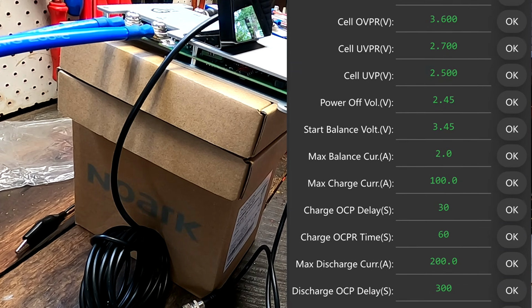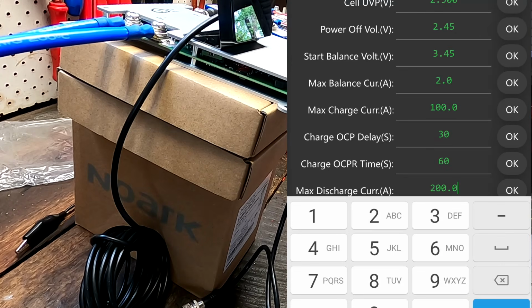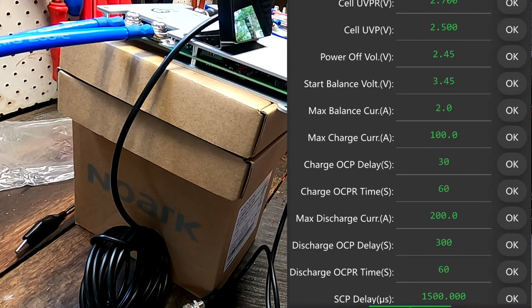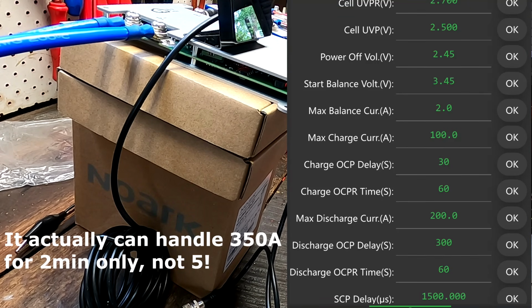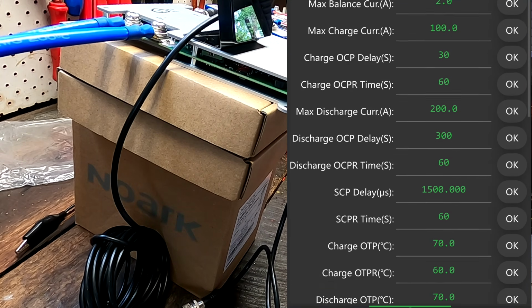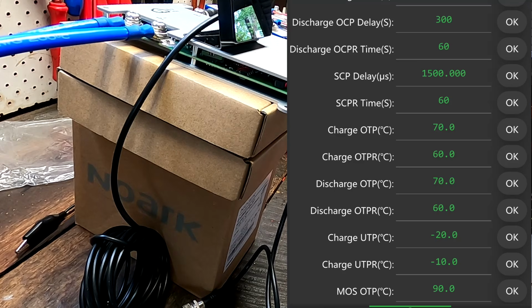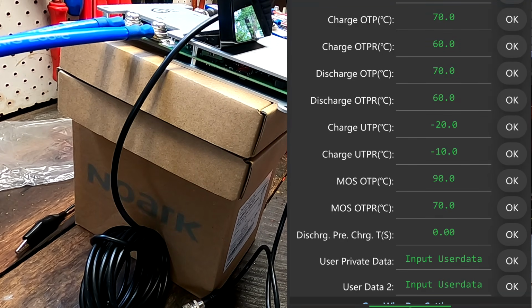Okay, max discharge current 200 amps. Yeah, that's correct. Discharge over current protection delay 300 seconds, that's 5 minutes, exactly what the BMS can do. Okay, all the temperatures, I'm not too worried about it at the moment.